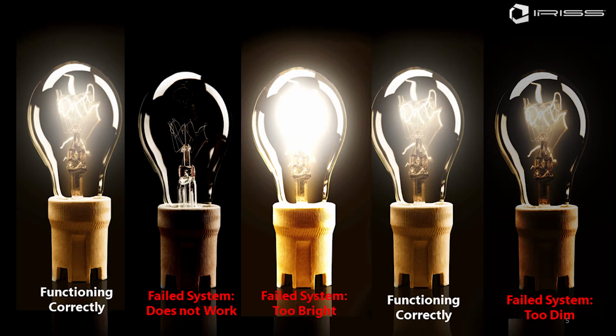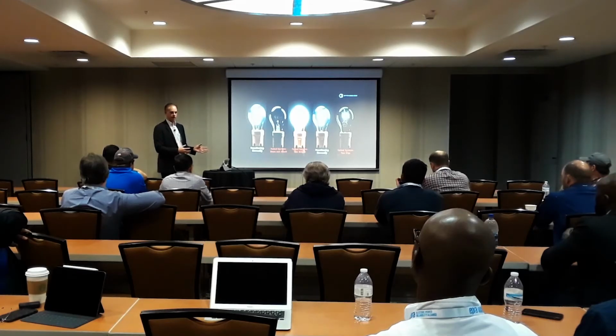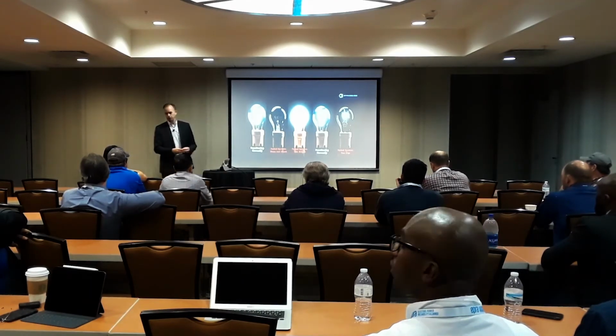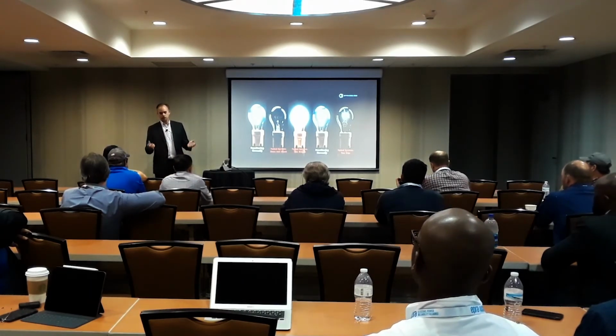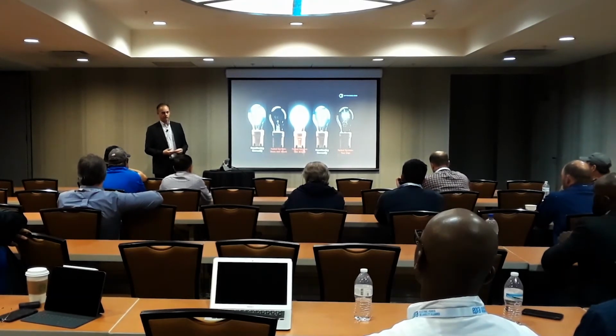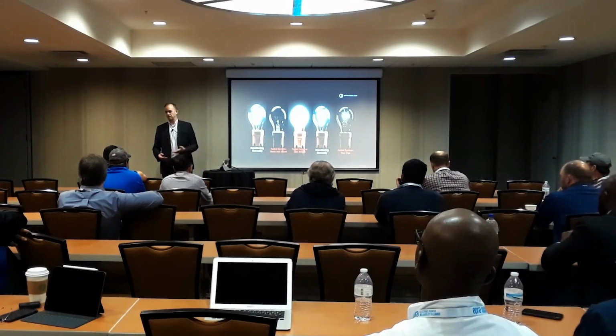Right? So if I'm doing infrared, if I'm doing ultrasound, et cetera, most of these things I need to do with the equipment energized. There are some exceptions. There are some things that we can do de-energized. Transformer oil sampling is a good example of that. Doesn't matter, right? The transformer was on within the last, I don't know, days. It's probably fine to take an oil sample, okay? Visual inspection obviously can be done with the equipment de-energized.